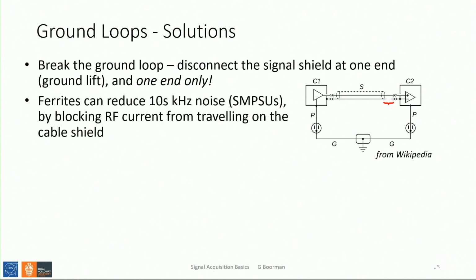Ferrites - if you've got RF type noise from switch mode power supplies, you can get a little ferrite, which is basically iron dust glued together. You can loop your cable a few times through that, and that is extremely effective at blocking RF. So if you know you're picking up RF from somewhere, you put ferrites on, ideally both ends of your cable, but certainly on the end where you're doing your measurements.